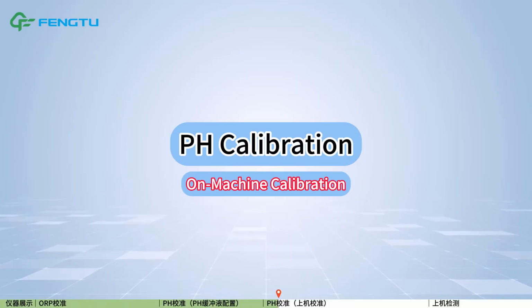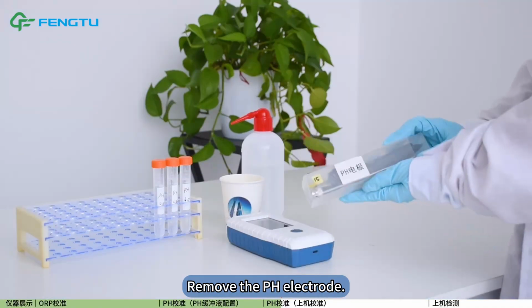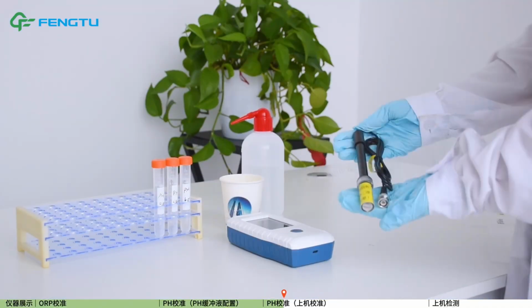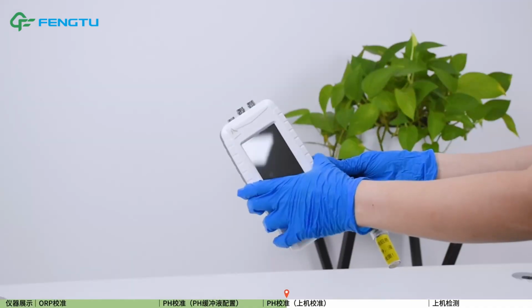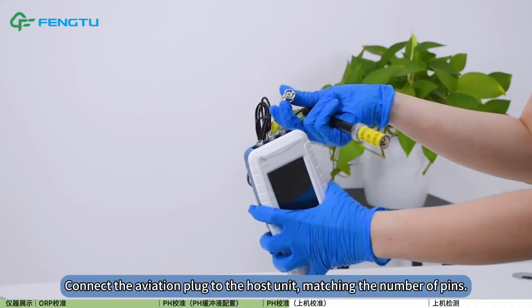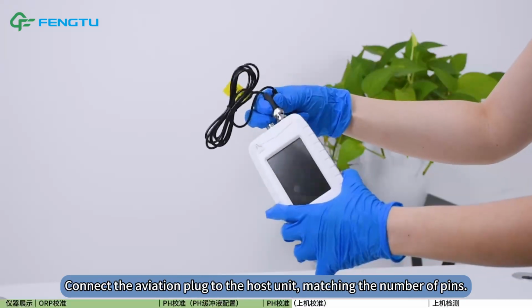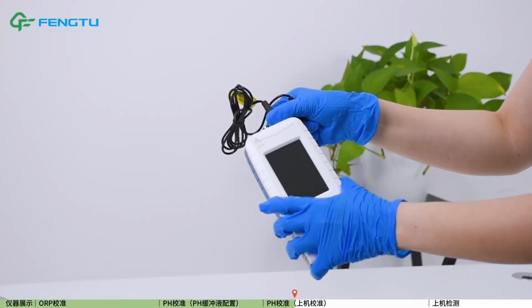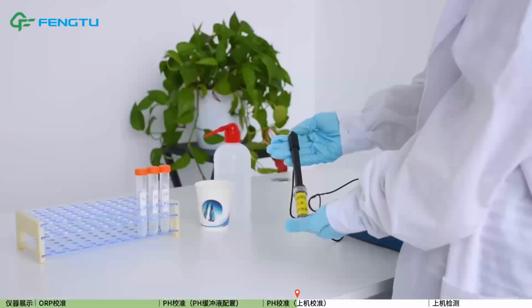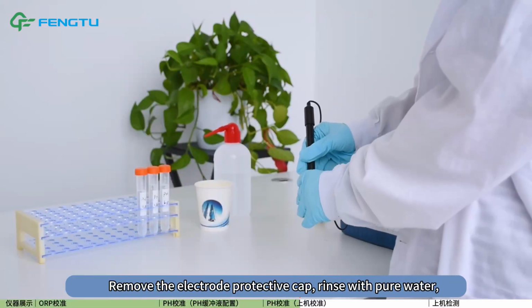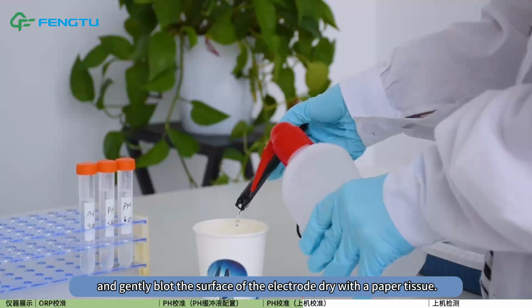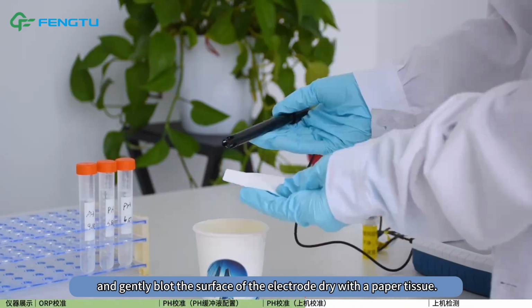pH calibration. On machine calibration, remove the pH electrode. Connect the aviation plug to the host unit, matching the number of pins. Remove the electrode protective cap, rinse with pure water, and gently blot the surface of the electrode dry with a paper tissue.